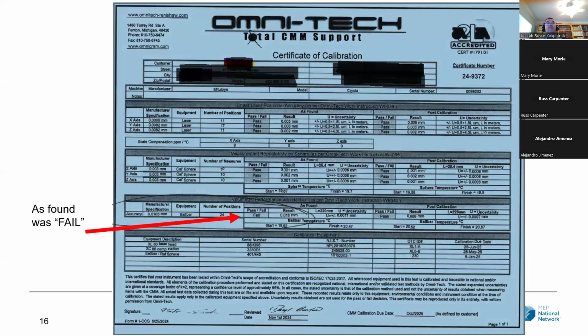But here's an example of an outside lab report that comes back, and this is of a CMM, and the as found was fail. Somebody needs to identify this. The calibration company may identify this when they're here and say, hey, the as is was out and we've calibrated it. But typically they don't. They just give you the report. But somebody needs to look at the report and flag it and say, hey, it failed.